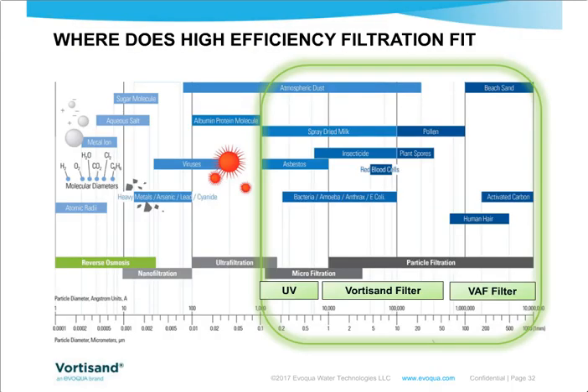And lastly, fine filtration utilizing a Vortisand filter isn't the only solution here. This is not going to solve all of your problems. It's not going to remove Legionella. It's going to assist in reducing nutrients for that Legionella to grow. So it's important to understand that submicron fine filtration is just one component of your overall solution for your process needs. We still like to see a larger screening technology prior to Vortisand's fine filtration.